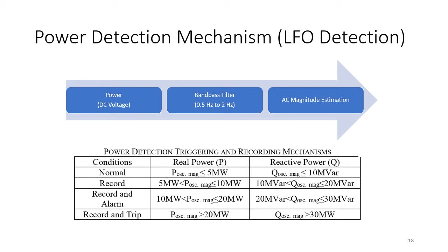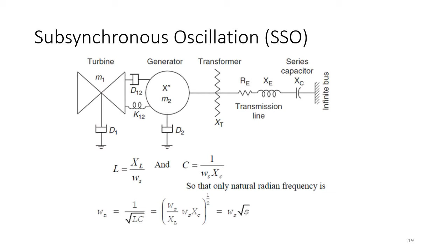The next detection mechanism is called SSO. I don't know how many of you have heard about this. It's called subsynchronous oscillation. Normally in a power system, we have a generator and transmission lines, and to improve the transfer capacity, we add a series capacitor in the transmission lines for compensation. It's called series compensation. When you put a capacitor C in the system, you have inductance L in the transmission line, so when you have an L and a C, you have a natural frequency. When that natural frequency is the same as the mechanical frequency in your generator, it's going to oscillate. That's the basic definition of SSO.